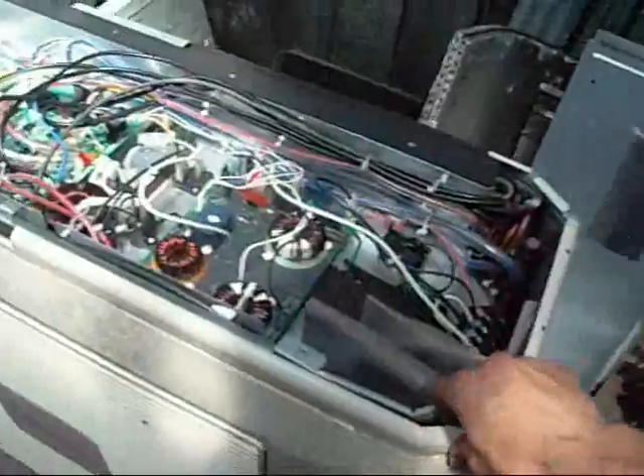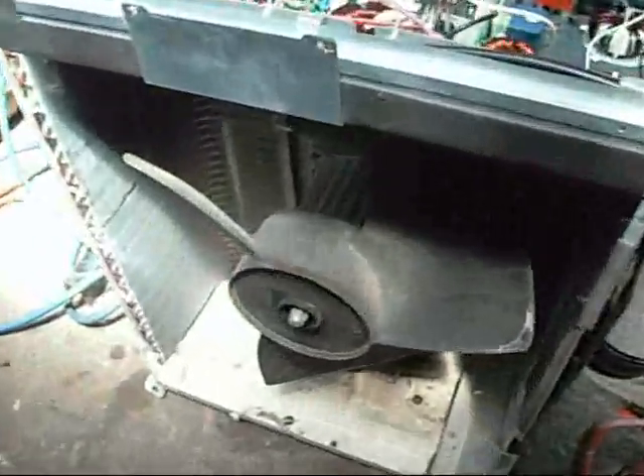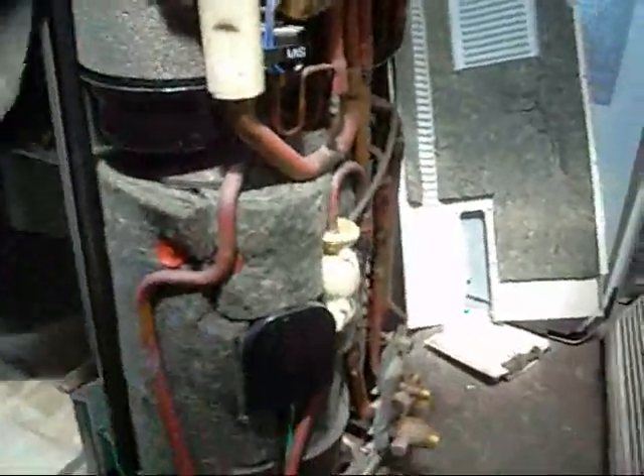I'll take this front off — I think it's still held on somewhere. Now we're getting down to it: a monster fan motor with a three-layer coil. That's one of the reasons why it's so heavy. The other is this — there's a big accumulator for the suction line, and I'm pretty sure that's a DC scroll compressor.